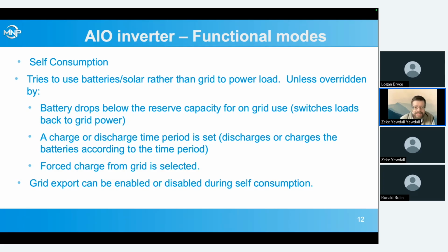Third way we can override self-consumption is if you select force charge from grid. This is really for when you're doing mostly self-consumption, but say you've got a big storm coming and you suspect the grid might fail. You want to top your batteries off to be ready for a possible power outage. You hit force charge from grid, it'll charge the batteries up from the grid. This overrides self-consumption, and it's also a one-time thing. So once it reaches full charge, that'll toggle back off so it doesn't stay on. So that's something to know about that, is that it's not like a permanent setting. It's like a one-time, let's charge these up to get ready for a power outage. And then once it goes back into normal operation, it's going to go back into whatever you had it set as before.